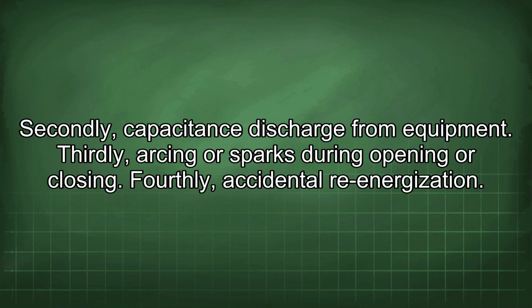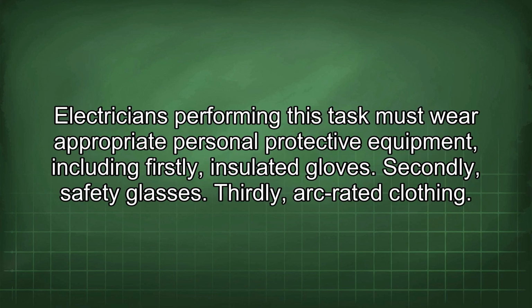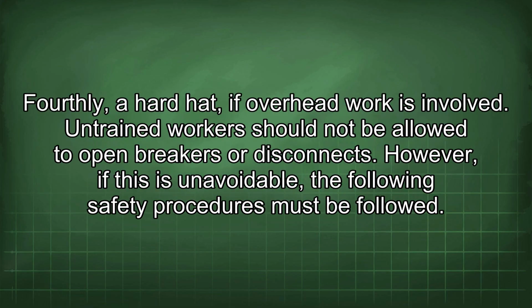Fourthly, accidental re-energization. Electricians performing this task must wear appropriate personal protective equipment, including firstly, insulated gloves. Secondly, safety glasses. Thirdly, arc-rated clothing. Fourthly, a hard hat if overhead work is involved. Untrained workers should not be allowed to open breakers or disconnects.